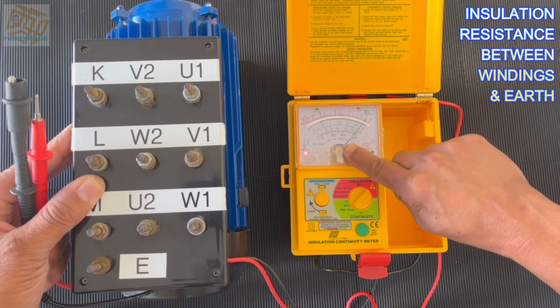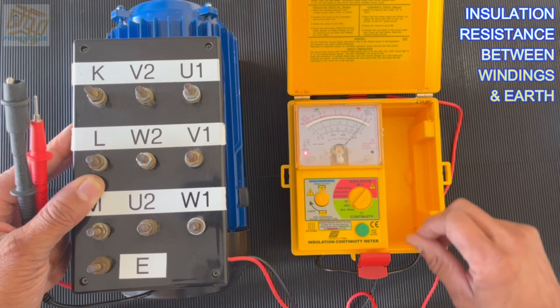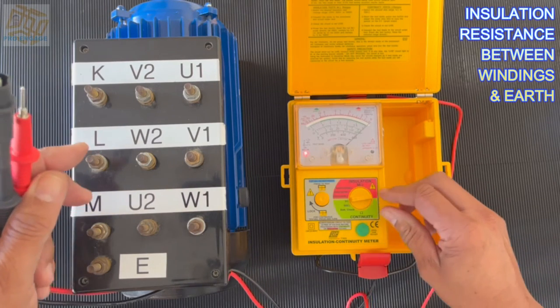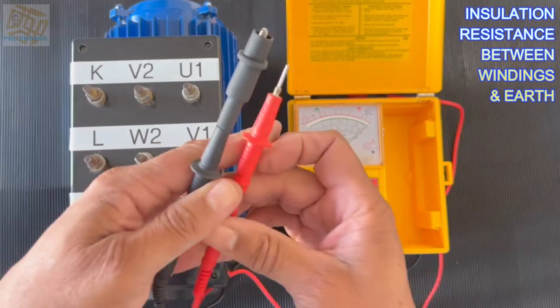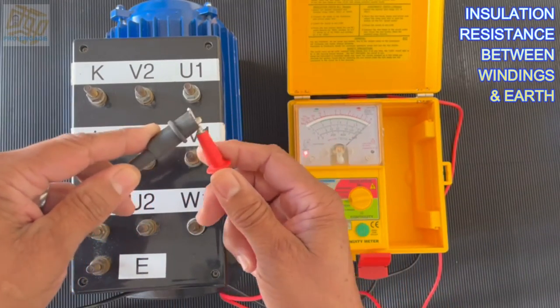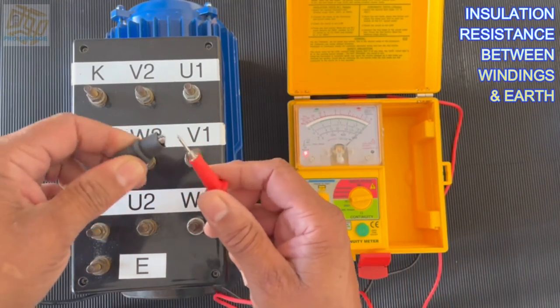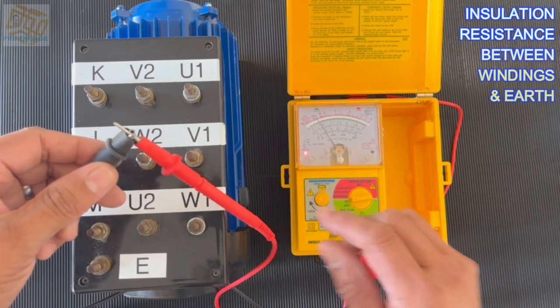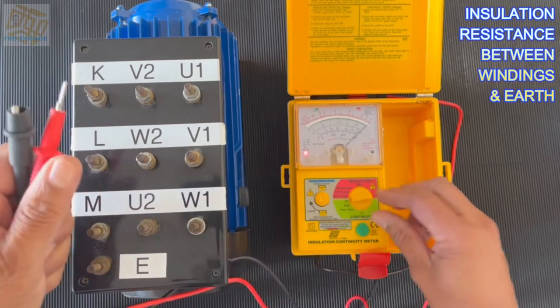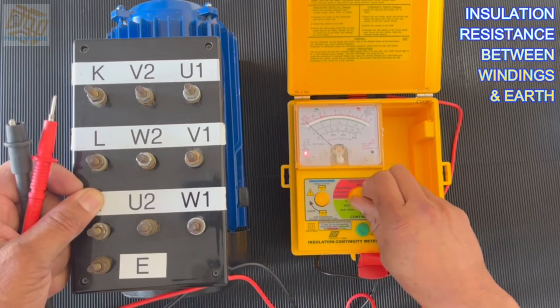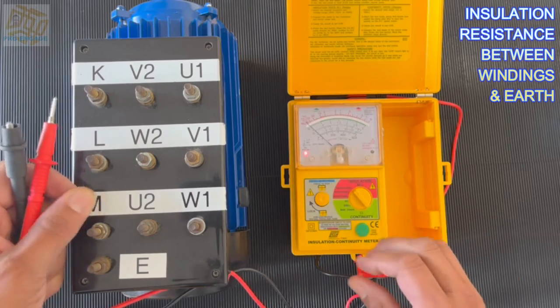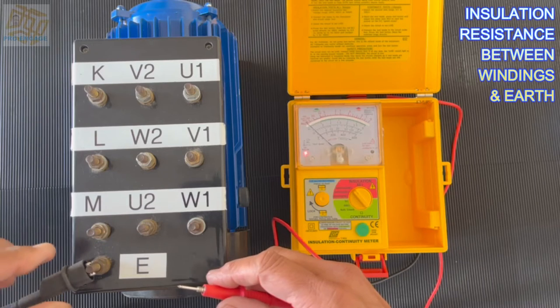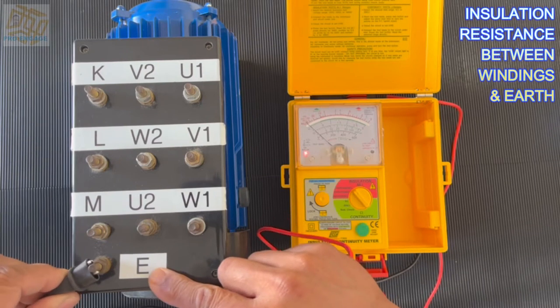I can see there the battery is good. If I want to see if the leads are good, I can on the ohm scale just put the leads together and make sure the leads are good. This is just normal general testing before we use our equipment or measuring testing equipment. Again we see that that's the ohm scale. We want to use the mega ohm scale where zero is contact, which is on the far right, and no contact is on the left where you can see infinity.